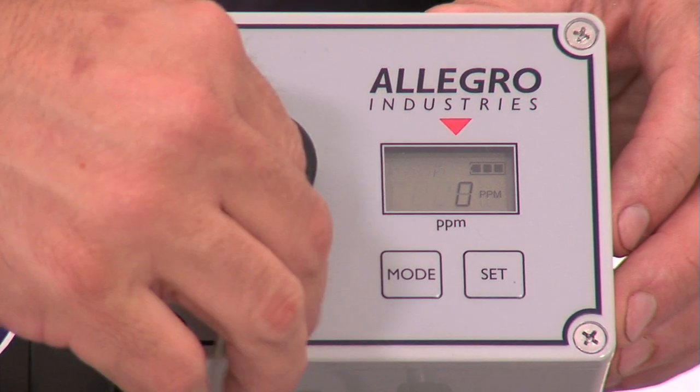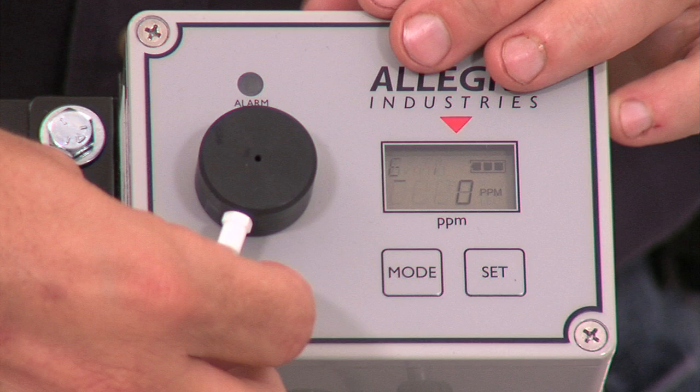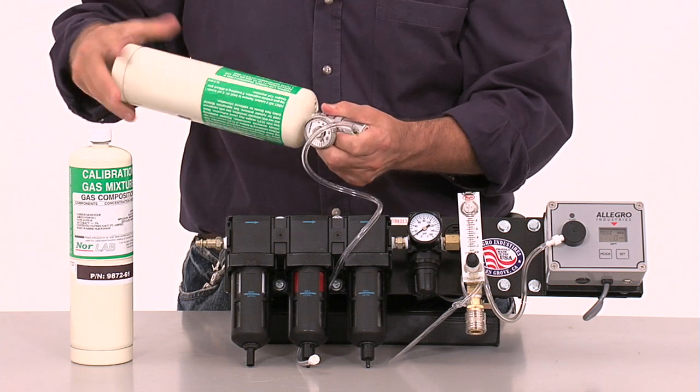Remove the luer fitting from the sensor cover and press the mode key two times to access the calibration mode. Connect the luer from the tubing on the regulator to the sensor. Assemble the zero air calibration cylinder to the regulator.